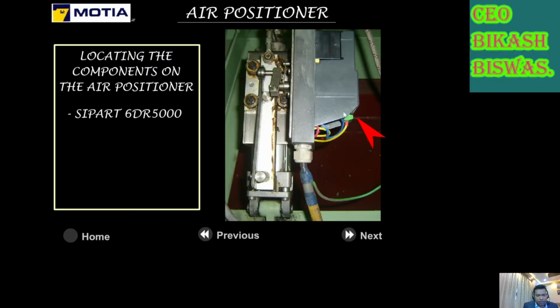See actually how it is. This is the current signal coming here. This is the SIPART positioner. This is the feedback mechanism. This is the linkage, and this is the roller. This roller is traveling on top of the taper plate, and thus it will move either in clockwise or anti-clockwise direction. It gives the angular feedback as per the actual position of the actuator. This is the roller. This is the taper plate.